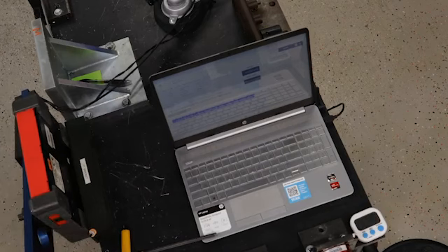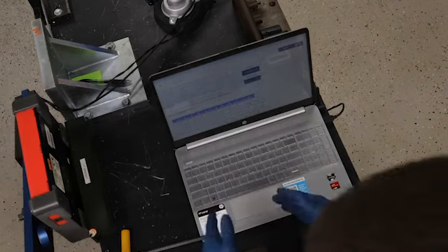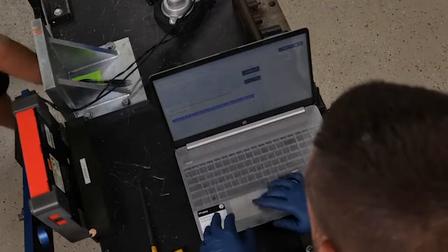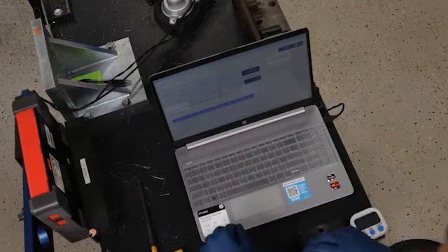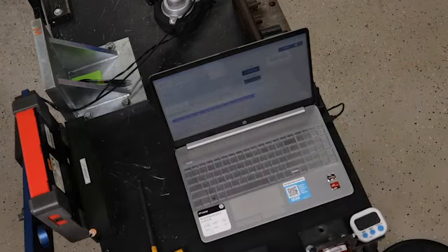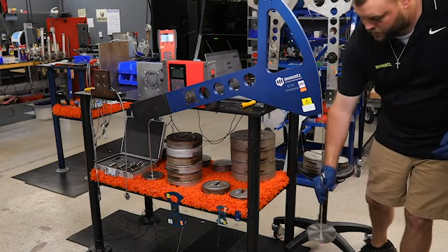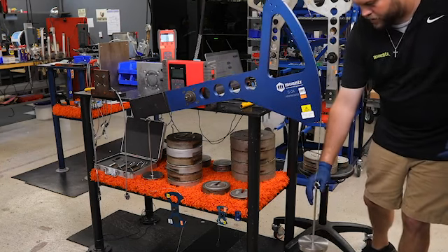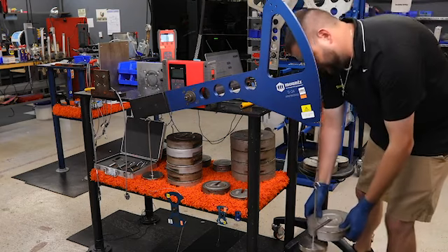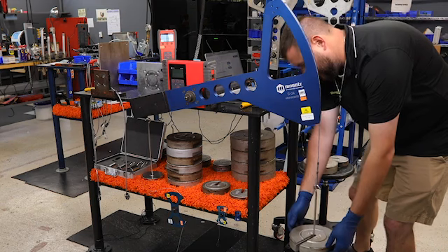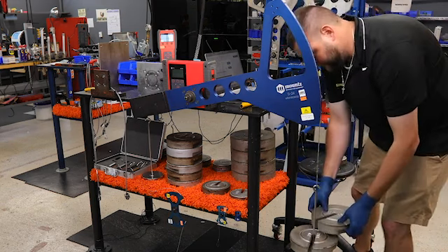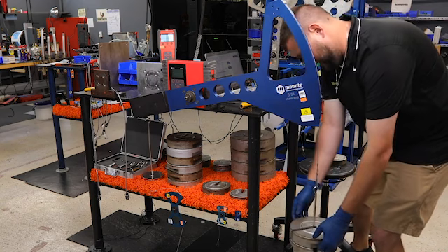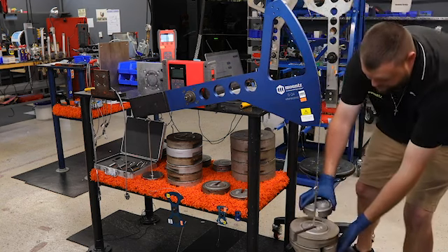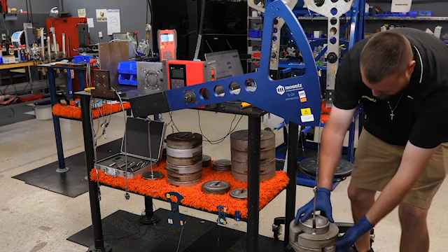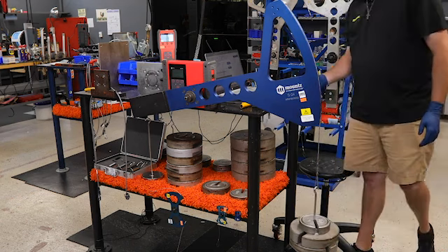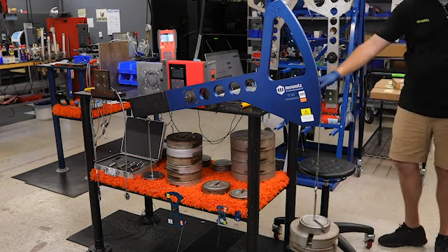And this is an image of the software program that we will use to capture the information and to program the actual information onto the ARC2 chip, which is located inside the sensor. The first thing that is done is we actually need to exercise the sensor. So we put a 100% value or 100% weight onto the sensor, and then we let it hang there for about 30 seconds to a minute or so, just to exercise that particular sensor.